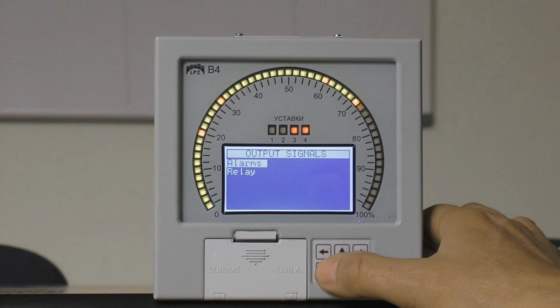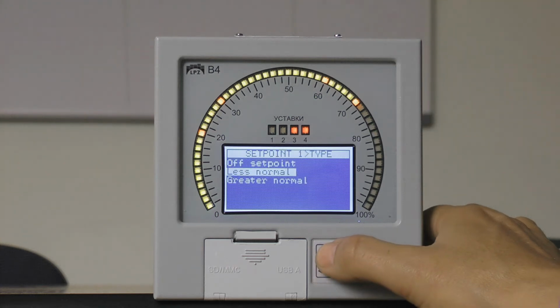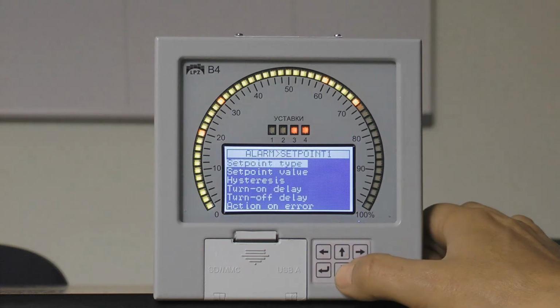Set points are control points within which it is necessary to monitor or adjust the input signal. Set points can be switched off. They can be less than normal and greater than normal. For each set point, you have to set parameters. They include set point values, actuation hysteresis, turn on and turn off delays, and action on errors.